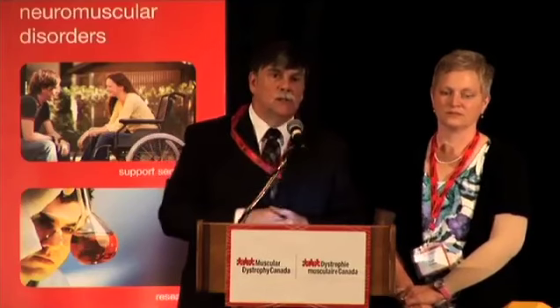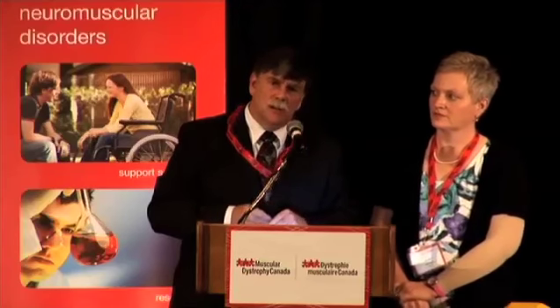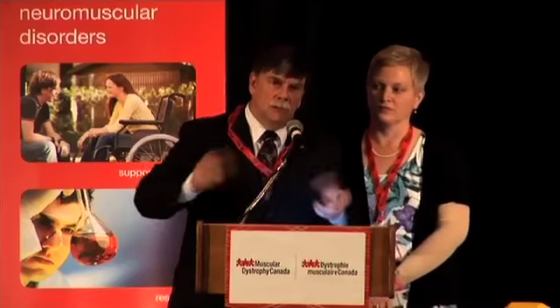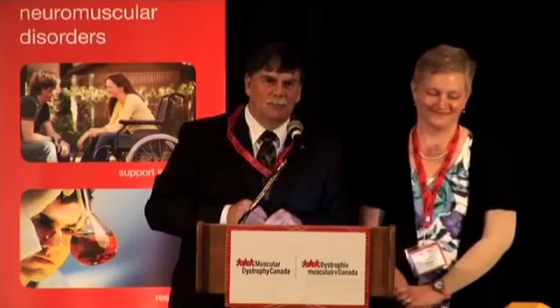The other thing that happens lately, in the last 10 years, is technology will outdo this ventilator in 2 years. There'll be something else on the market 3 years from now that will be the new fancy gizmo, and people will say, hey, this feels good, I like this. Advancements in technology will outstrip the ventilator in about 5 years. But preventive maintenance and overhauls at 1,000 to 2,000 hours, I know Respironics, I think they're $600 to $1,000 each, and what they do is they replace some of the key moving parts, except for the flow generator, which is the most expensive part, and that's what burns out in them. About 5 years.